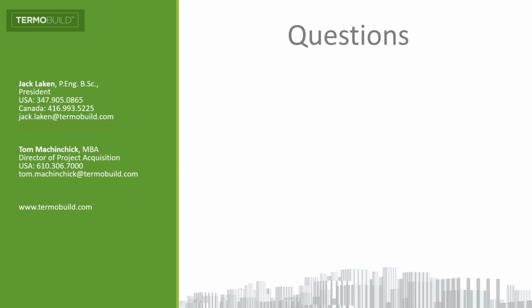That's true. Which climate zone is best for integrated ventilation design? Is there a limitation on that? Is it better in some and not so good in others? We have buildings in cold climate, we have it in hot, and we have it in hot and humid climate zones. So it's just a question of engaging the mechanical systems that are suitable for this climate zone with the concrete floors or precast floors to extract value that is otherwise lost.